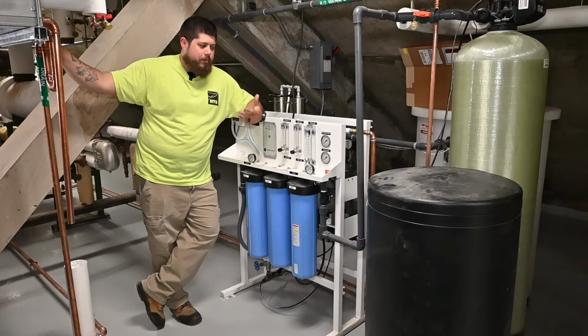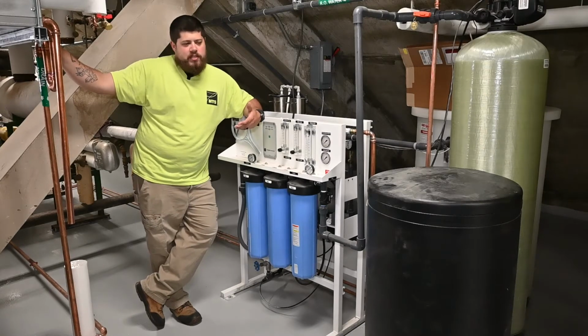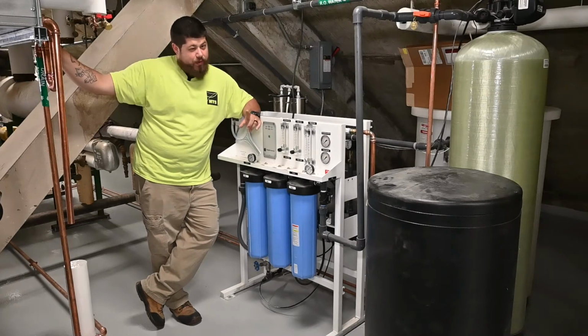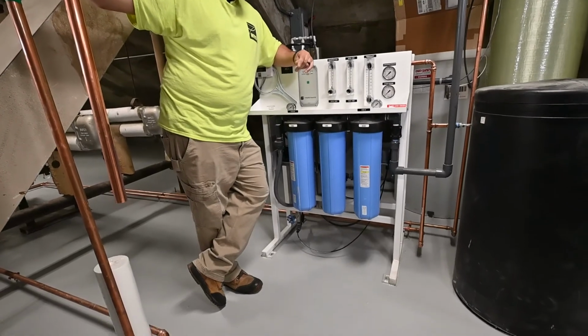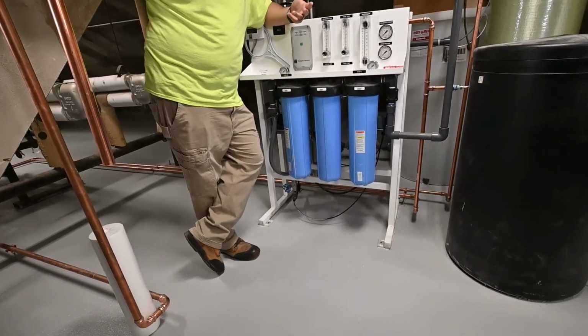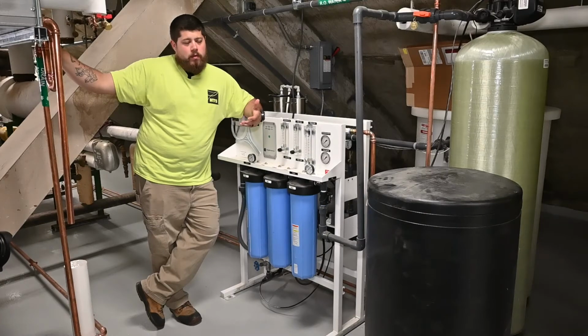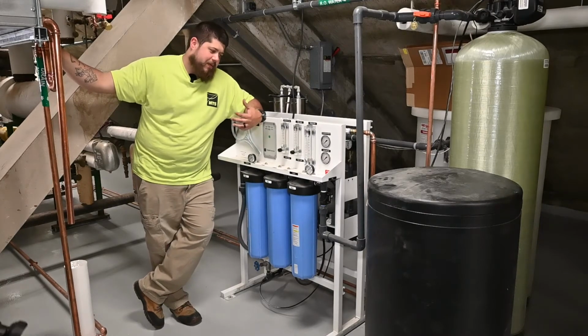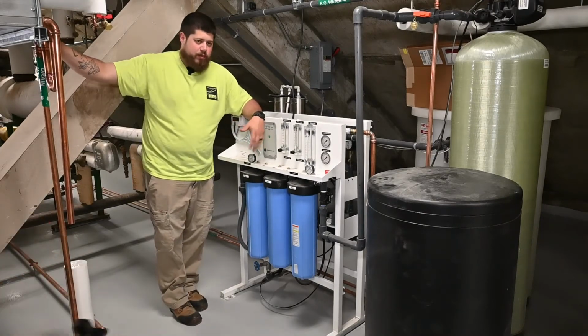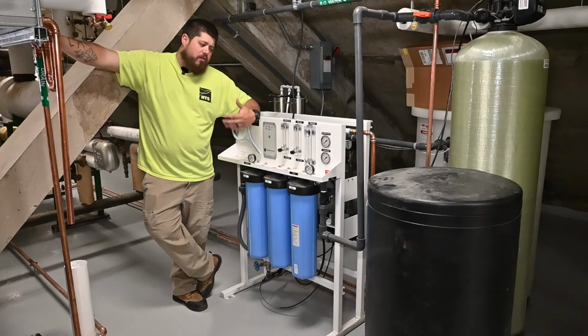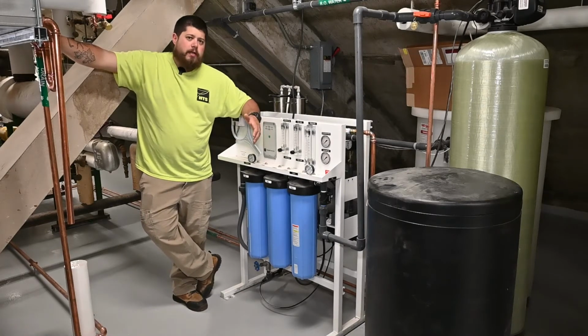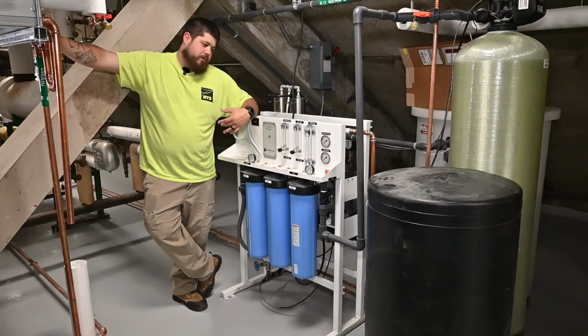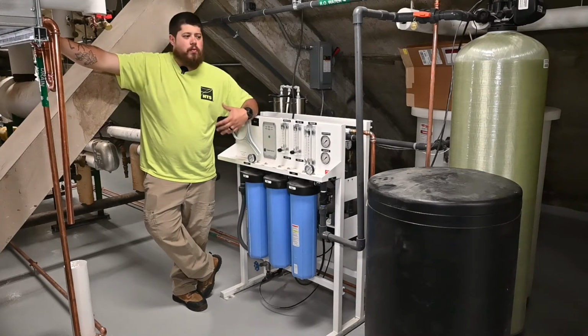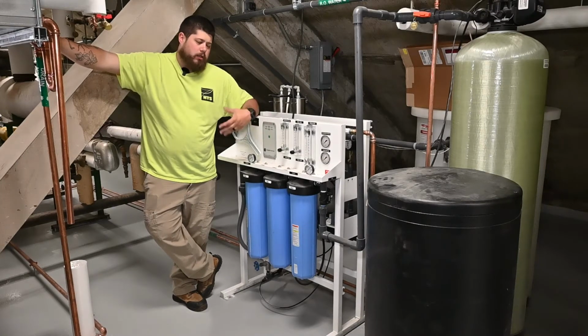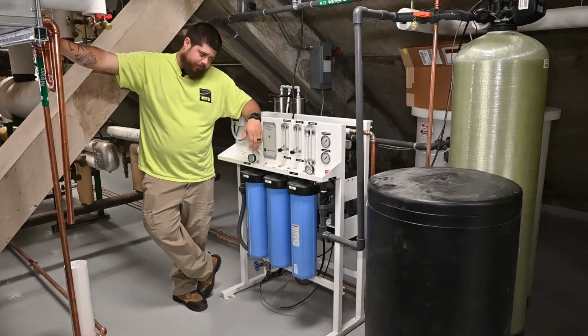You'll see a spike in the system pressure. The system pressure, I believe, is dialed in for 125 from when we started up this unit. If it starts to rise, you don't want to go above 140. So if you start getting closer to that, that's a recommendation to replace these filters. If you're going to replace one, replace all 3. There's no sense in replacing one just because you believe that's the one causing issues. You want to keep them all in the same loop as far as operation.